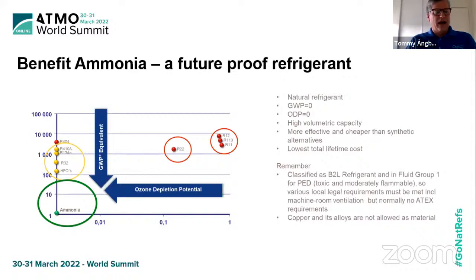But there are no ATEX requirements like for other flammable refrigerants. But we need to maybe have good ventilation and follow the local rules. And copper alloys cannot be used together with ammonia. But still we like it. It's a future-proof refrigerant and very beneficial for energy efficiency.